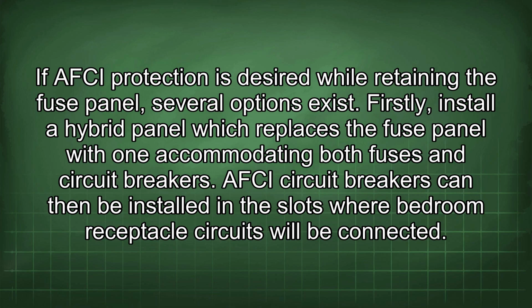Firstly, install a hybrid panel which replaces the fuse panel with one accommodating both fuses and circuit breakers. AFCI circuit breakers can then be installed in the slots where bedroom receptacle circuits will be connected.